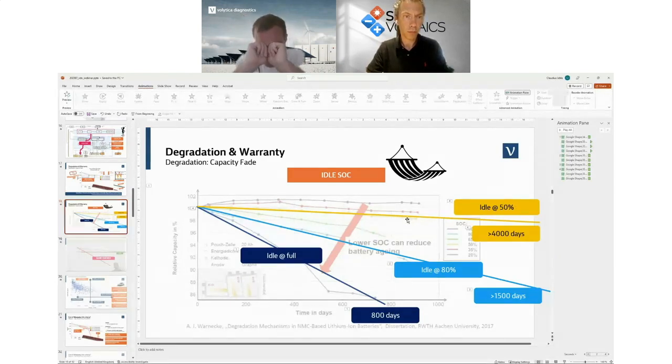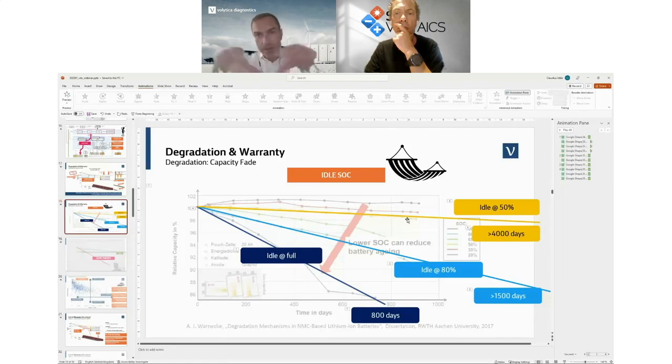The 30% is a compromise between charging too low, as you said, and also transporting it. There are transport regulations in place that limit it to 30%. So in a way, you're right. It's a mixture between not discharging too deep, which can also be less beneficial, but also external factors, how you are allowed to transport that.